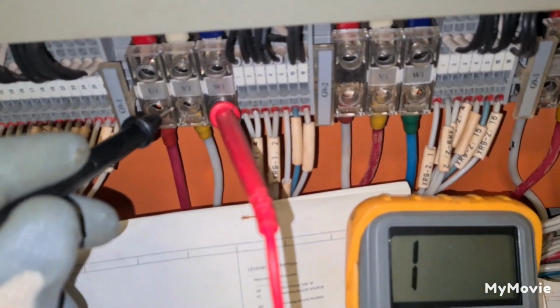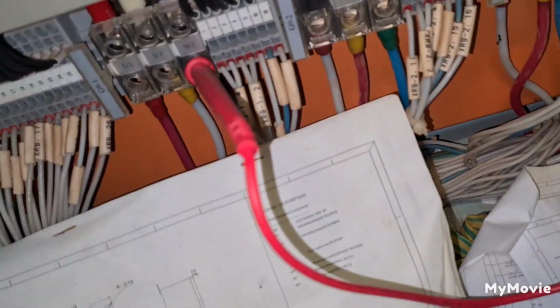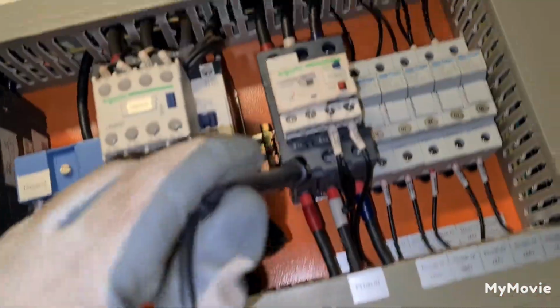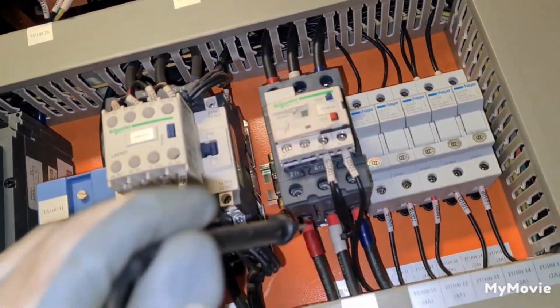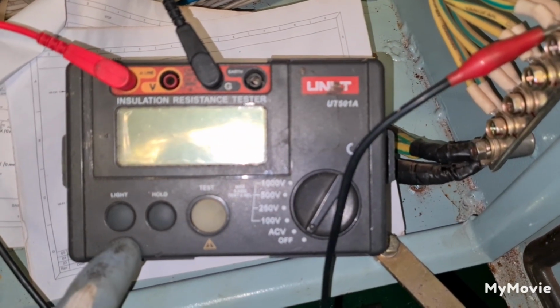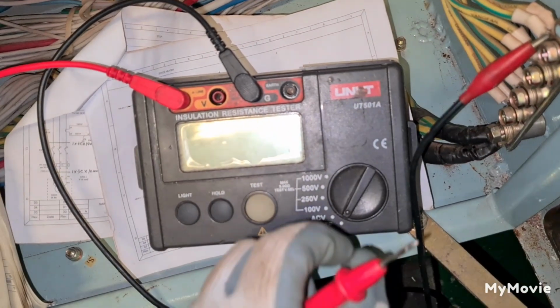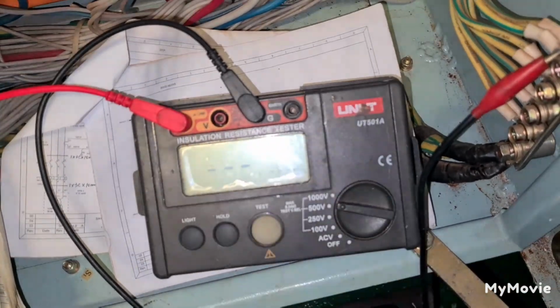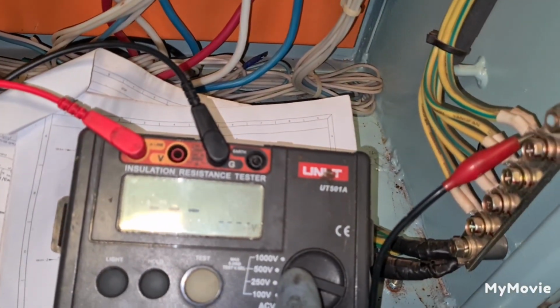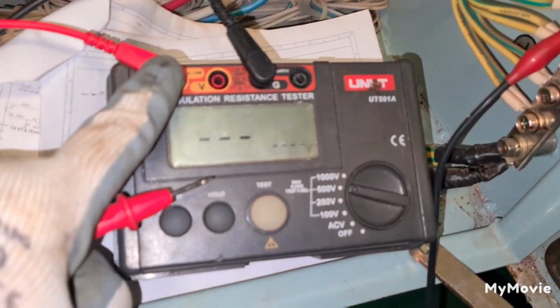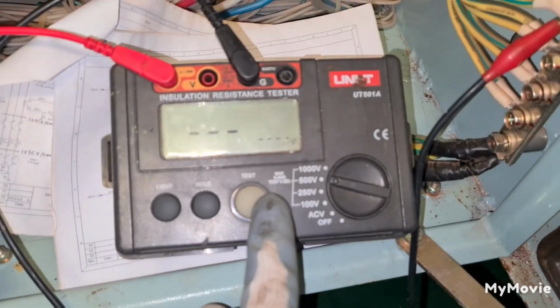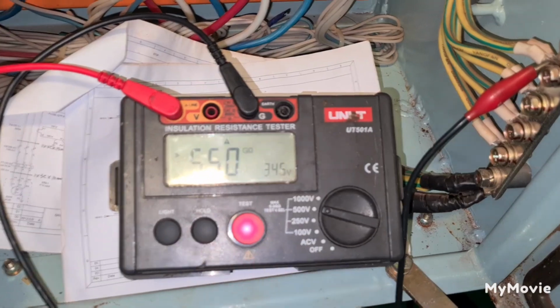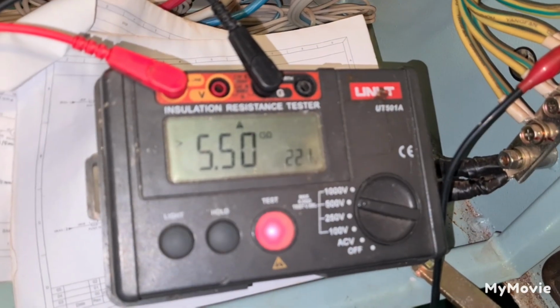So this is the fourth one with the contactor over there. The fourth one here, we test the continuity. Okay, so guys, this is our insulation tester, and we are going to put it on 1000 volts or 500 better. Then you must connect G on the ground, and this is for the line. So we can press this one and we can do a test. But before doing a test, you must record a testing.